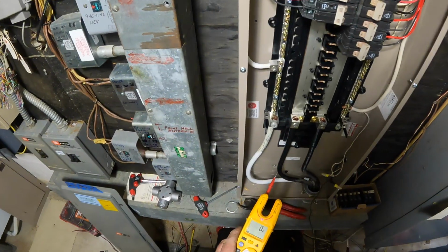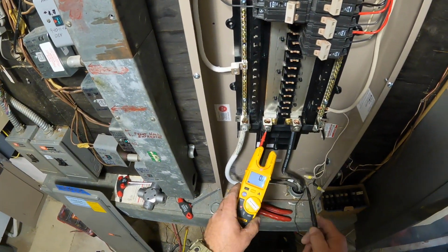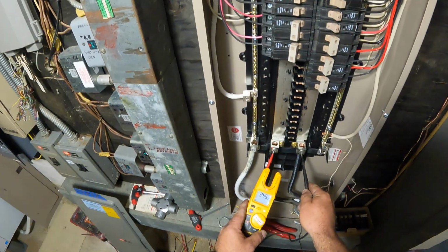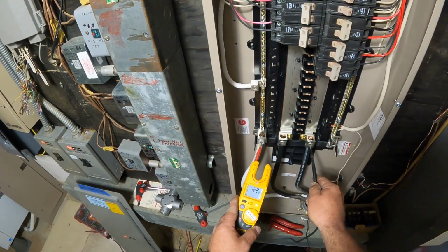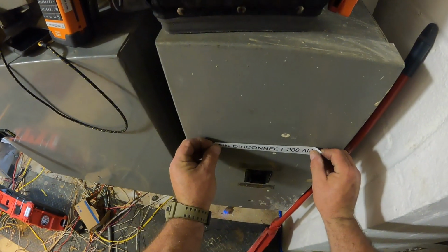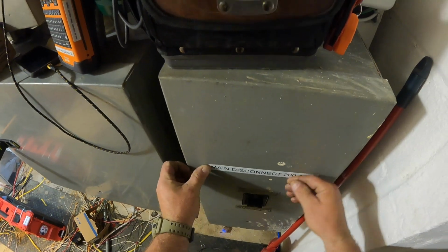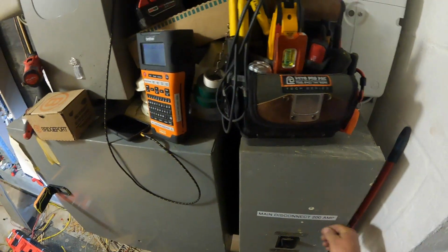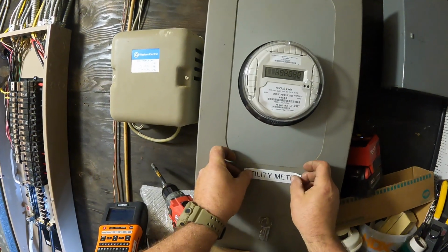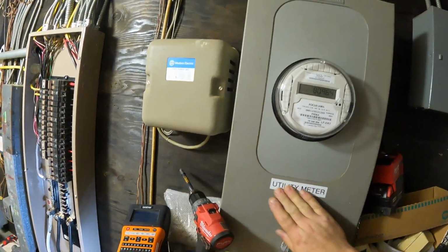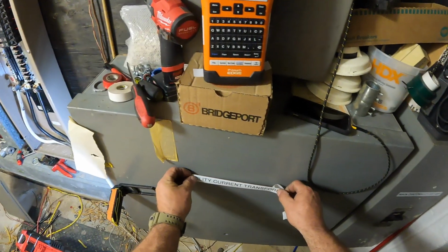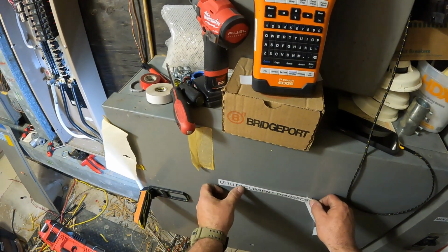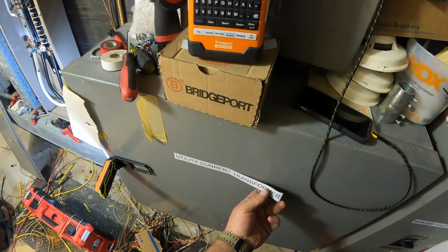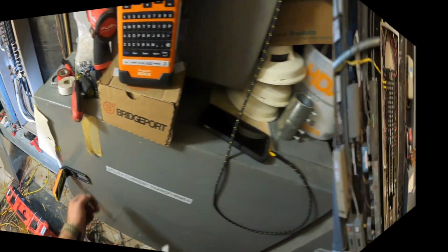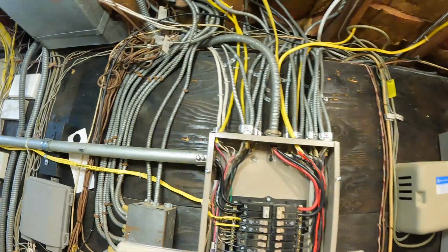Now that the main breaker is on, I'm going to verify my voltage between both hot legs - I have 245 volts, and 122 to each leg, which is exactly what I'm supposed to have. Before I go, I want to identify all this equipment: that's the main disconnect, that's the utility meter, and that's the utility current transformer box. Then I just need to take the knockouts out of the panel cover and put the cover on, and we'll be ready to go.